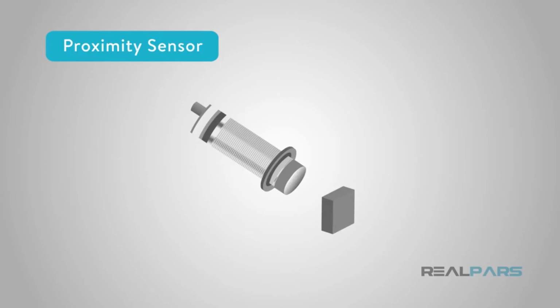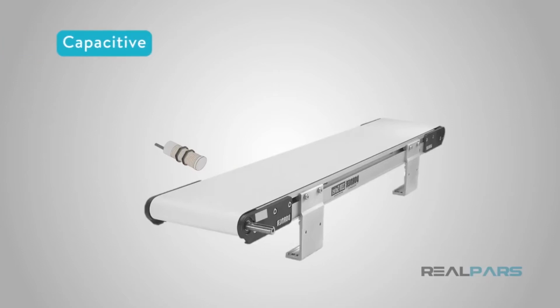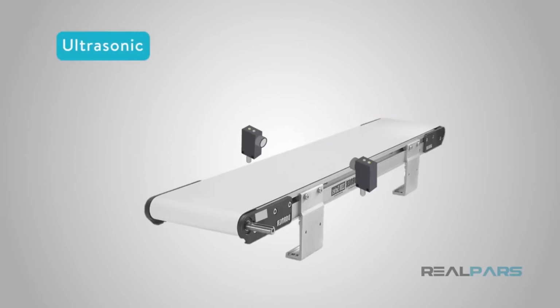Let's look at a few examples of these kinds of sensors. Proximity sensors are used for detecting close metal objects using magnetic fields. In many environments, these have replaced limit switches in position sensing applications. Capacitive proximity sensors are like a proximity sensor, but for detecting non-conductive materials. They are very sensitive to contamination and historically have not been very dependable. Ultrasonic proximity detectors detect solid objects using higher frequency sound but are very susceptible to environmental conditions and dirt. We don't use them often, but they can solve sensing problems nothing else can.